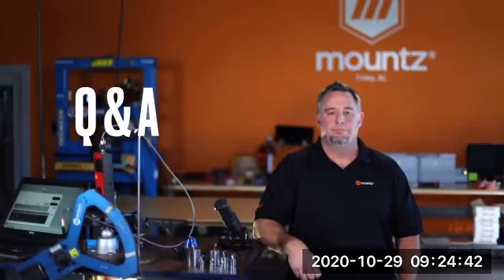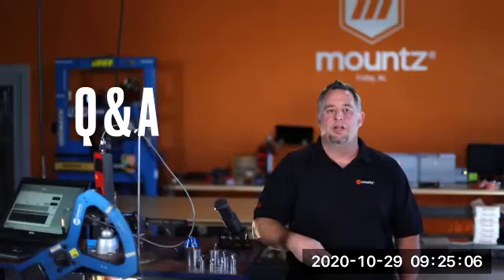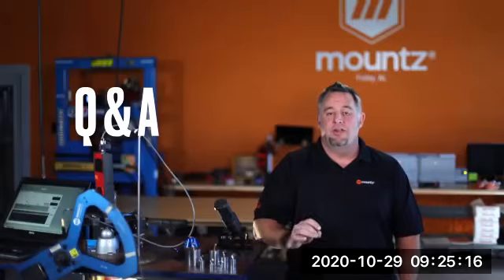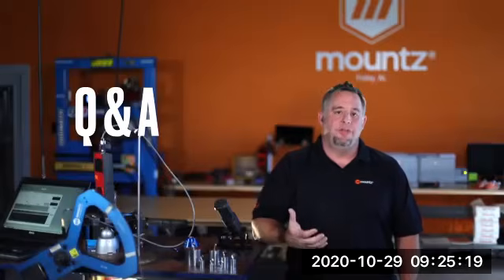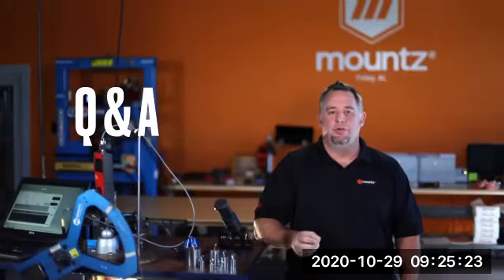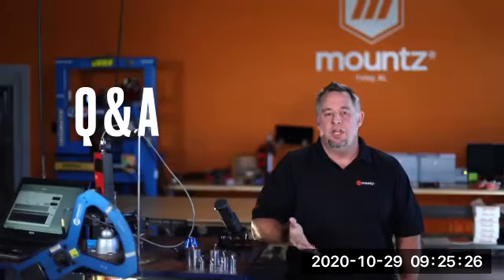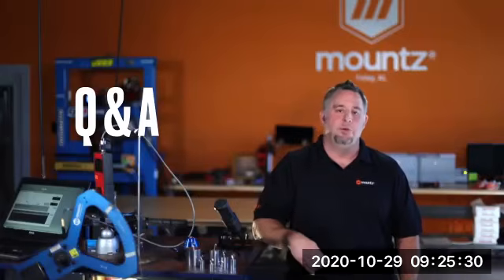I have a question from Luis. I'm not sure if we'll be able to answer it based on the standards here. According to DIN 51309 standards, you must calibrate the equipment depending on the class of transducer. Why would you only calibrate 3 points, and what classes are the transducers? There are different calibration processes that would require more than 3 points. On the ISO 17025 cert, that's a 5-point calibration, while the Z540 is a 3-point calibration. So it's dependent on what standard you need it tested to, as to how many points you would be using.